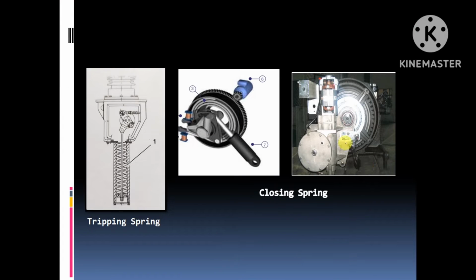The breaker we are discussing in this topic is the ABB make LTB 245E1. This is the tripping spring. This is a helical type spring. It is kept inside a cylindrical enclosure and the mechanism is connected to one more neighboring mechanism box. This is the closing spring. This is a spiral type closing spring. This is the model type diagram. This is the actual photograph. The closing spring will be installed here. This is the motor for spring charging. Here the 12 NO and 12 NC contacts will be there.